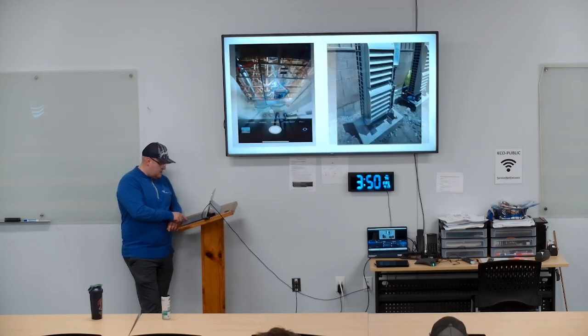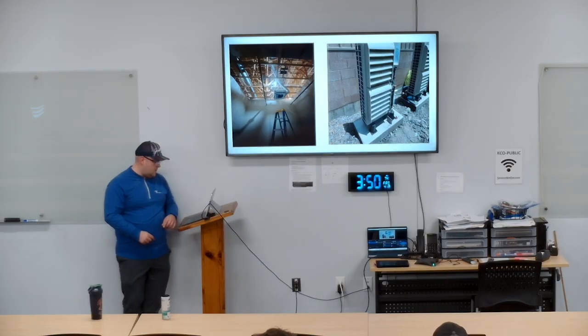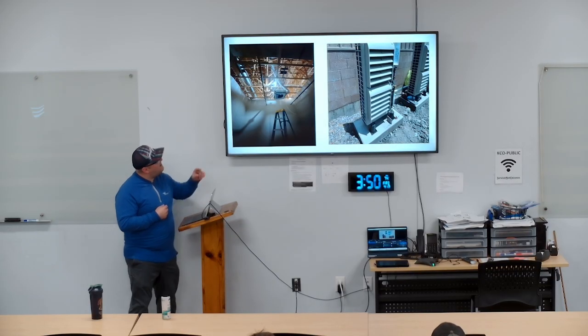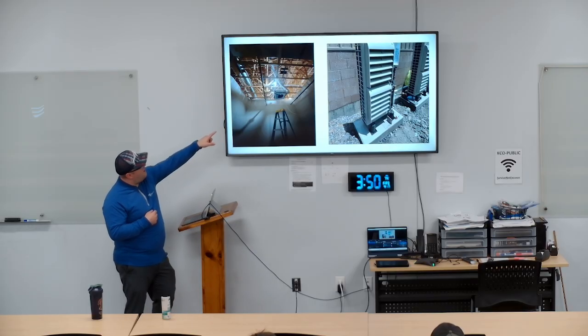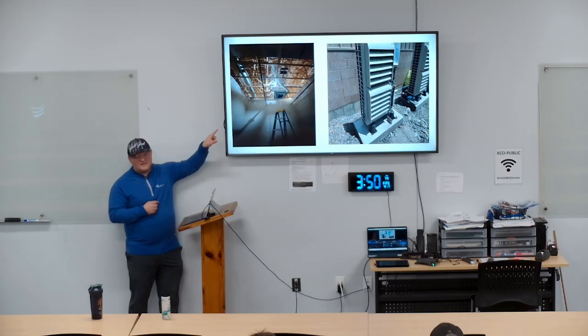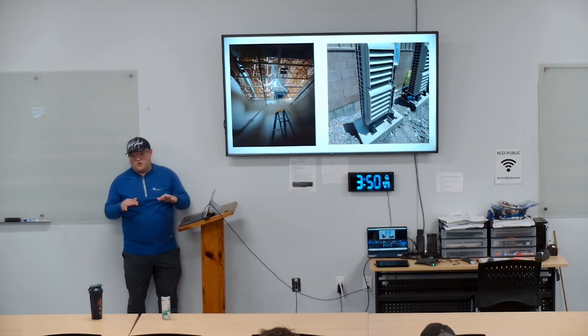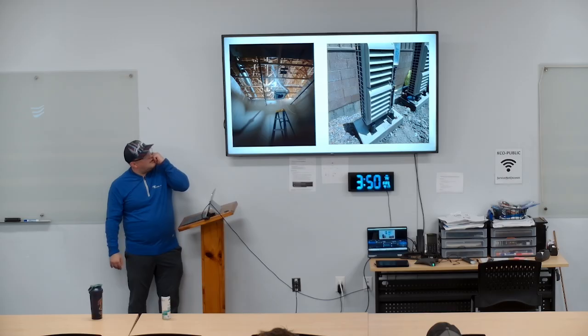And then lastly, oh. So this is what I was talking about when I was saying cassette. That's the left side. It was kind of hard to see. But I can tell you in that instance, that's gonna suck for the grid guy. He's gonna be mad at us. Because for everybody in the room, the cassettes are the hardest thing for us to hang, based on the fact that we don't have leniency on our condensate because the cassette has to sit in the ceiling grid. And in the ceiling grid, normally you only have a half inch of play because the grill goes over it and tightens below the ceiling grid.